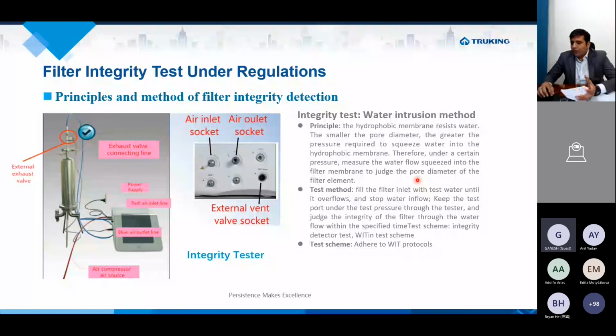Then in the method, how we do it: we fill the filter inlet with test water until it overflows, first point, and then we stop the inflow, second point. Then we keep the test port under the test pressure through a tester, such kind of equipment, and judge the integrity of the filter through the water flow within a specified test time. So it's linked with the water flow and the time that is stipulated on the device. We make a recipe for this during qualification. Then the integrity detector test scheme can be employed. Either the water intrusion test or the other test can be done. So we can adhere to the WIT, water intrusion test, protocols in this particular scenario to ensure the performance is adequate, and we can prove the integrity in our documents at the design stage.